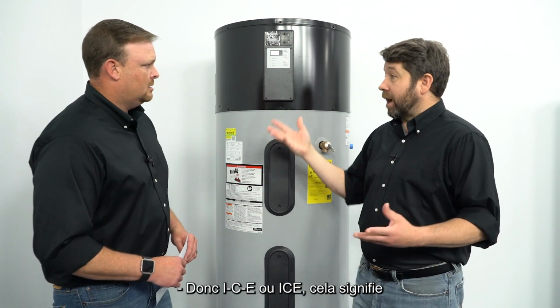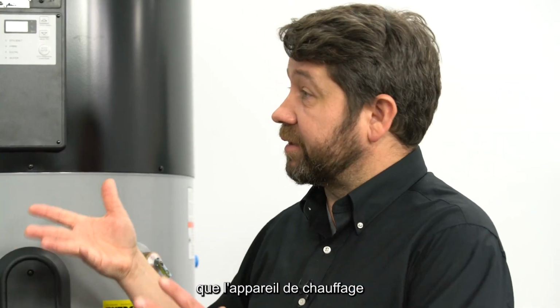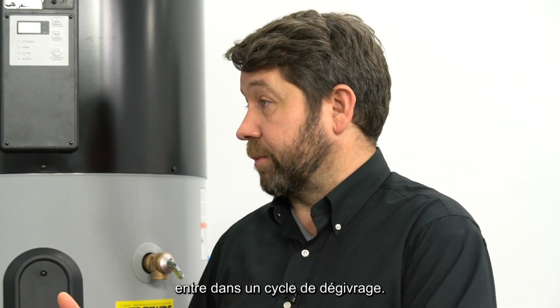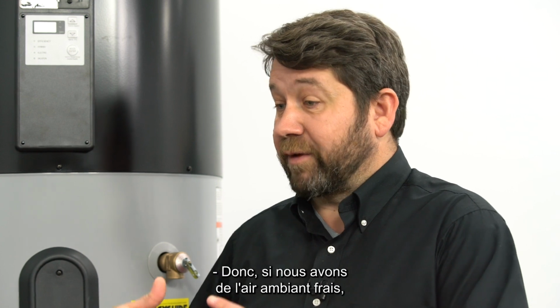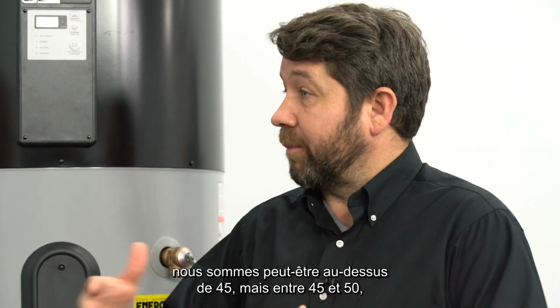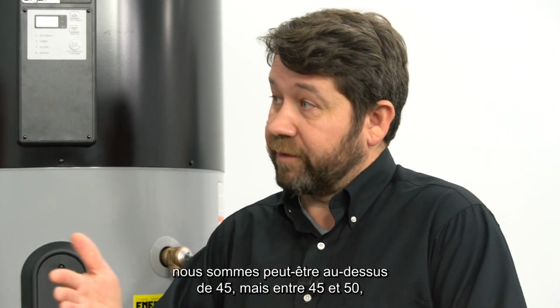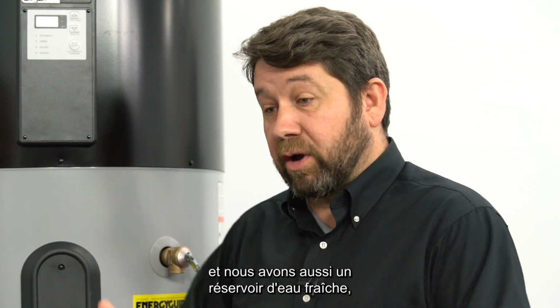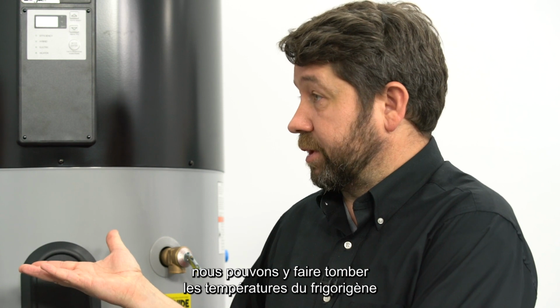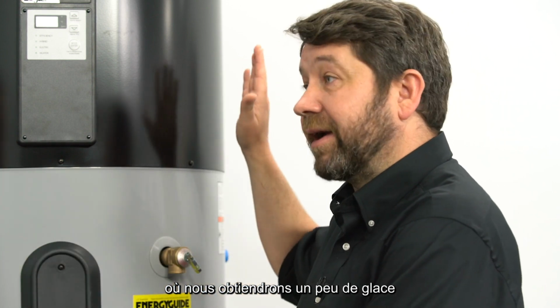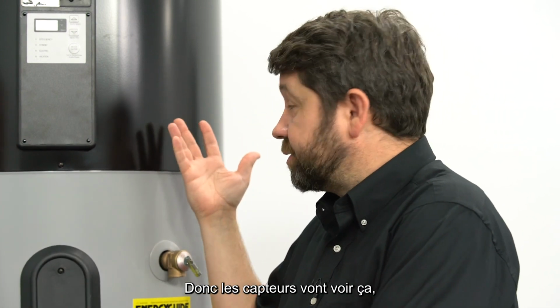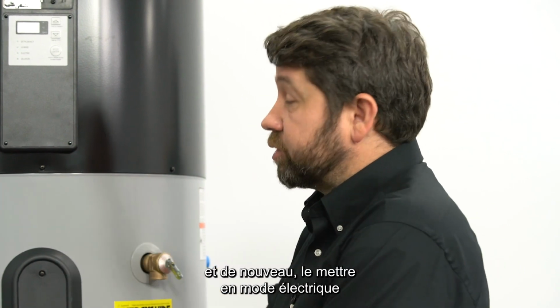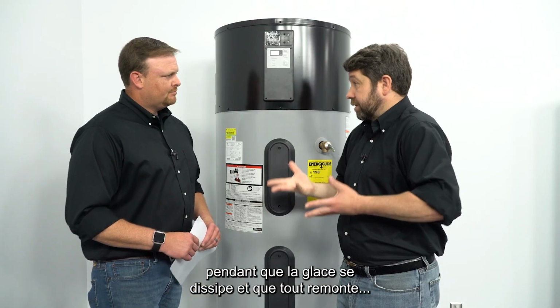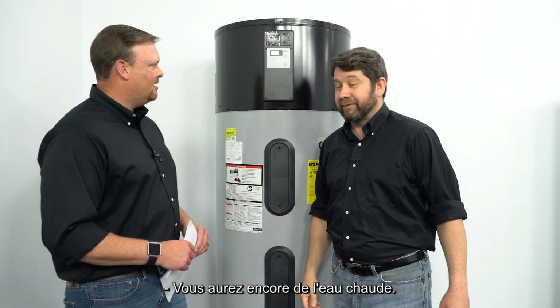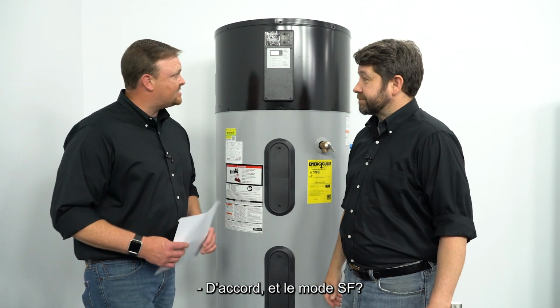ICE means that the heater is going into a defrost operation cycle. If we have a cool ambient air, we might be above 45, but somewhere between 45 and 50, and we also have a cool tank of water, what can happen is we can drop the refrigerant temperatures to where a little bit of ice will form on that coil. So the sensors will see that, and again, switch it over into the electric mode while that ice clears and get everything back up into the right range. Still have hot water. Okay, how about the SF mode?